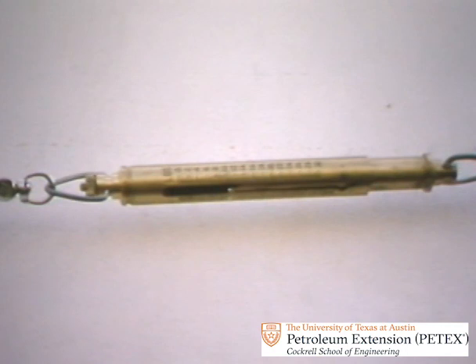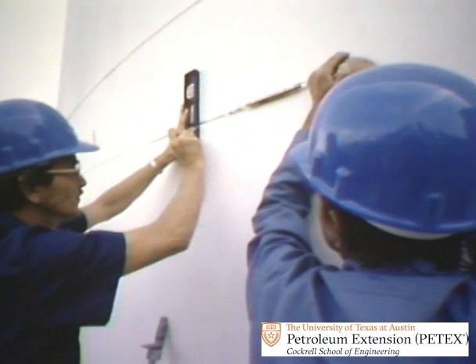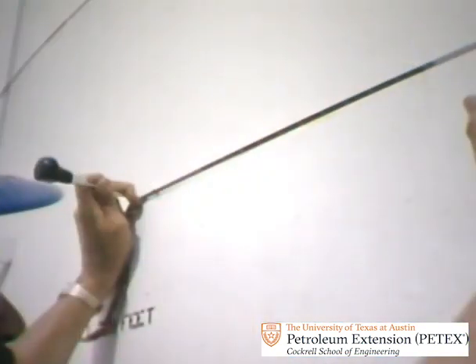A tension gauge tells the crew how much tension is being applied. Tension must be sufficient to hold the tape against the tank. Since the tank ring circumference is more than 100 feet, a crewman makes a vertical score on the shell at the 100-foot tape reading. Correct tension is still being held on the tape. After releasing tension and moving the standard tape forward, the crew carefully lines up the zero reading on the standard tape with the 100-foot vertical score. The tape is still on its path.